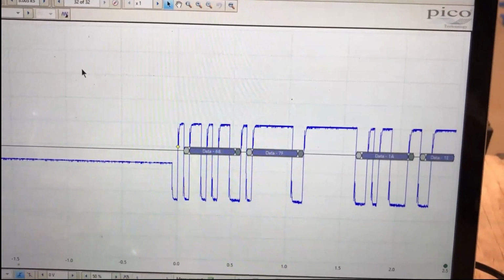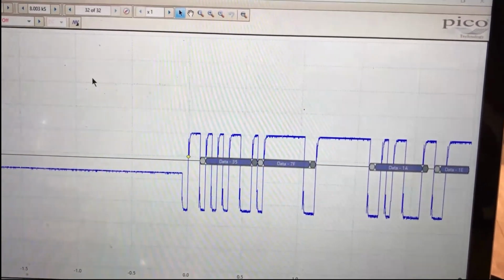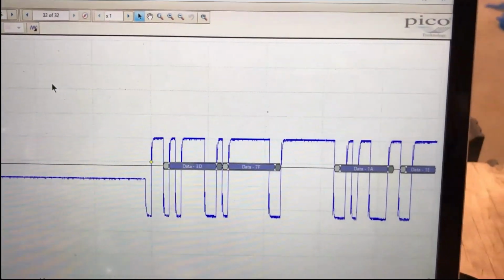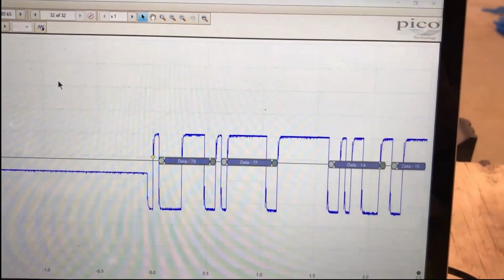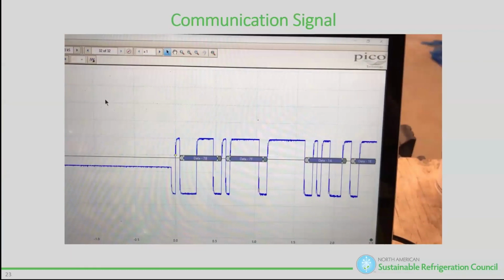So what did we do with this? This was on 40 cases on one Modbus network. How the hell are we going to troubleshoot that? What we did was disconnect case 20 and disconnect 21 through 40. As soon as we did that, the signal came up. We were good, so we said the first 20 cases aren't the problem.